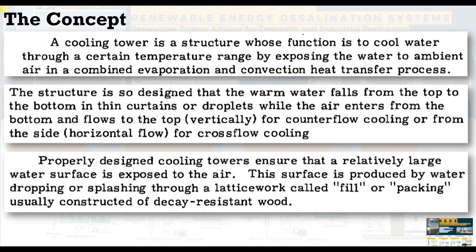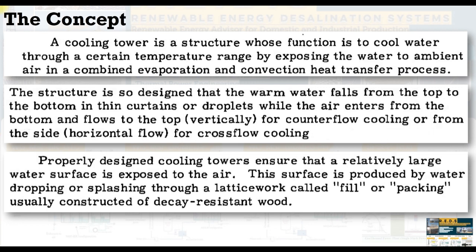The structure is so designed that the warm water falls from the top to the bottom in thin curtains or droplets while the air enters from the bottom and flows to the top vertically for counterflow cooling or from the side horizontal flow for crossflow cooling.